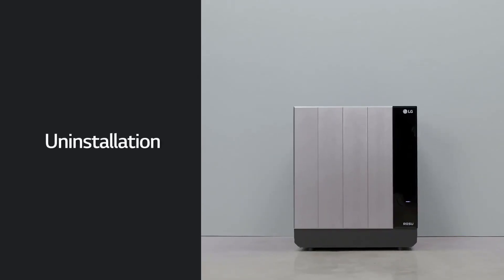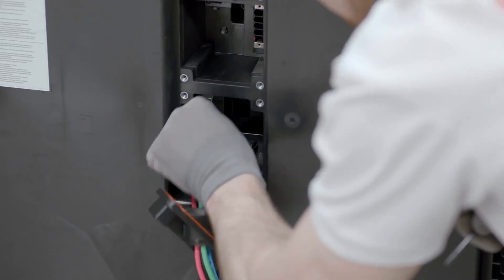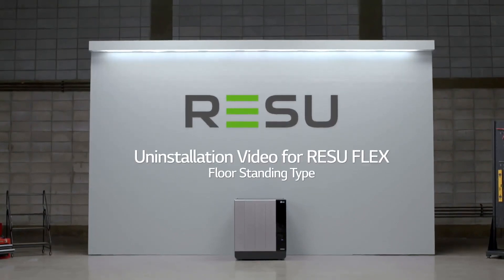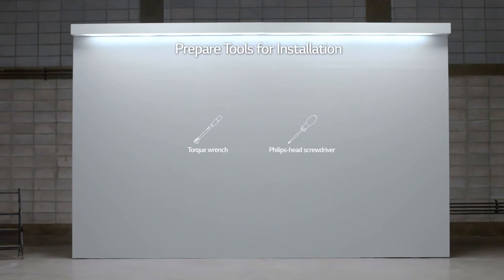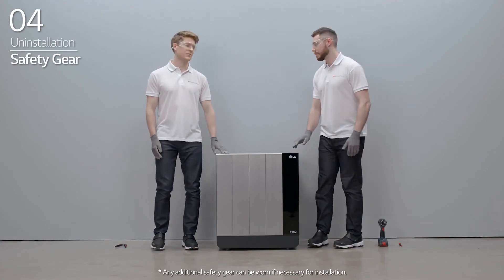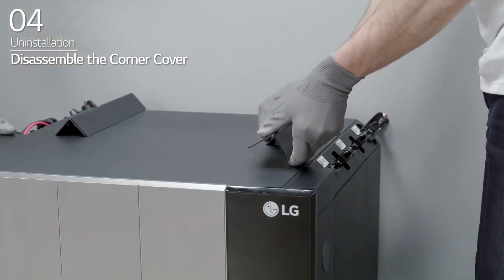Uninstallation. LG Energy Solution will show you how to uninstall the RESU FLEX. Before uninstallation, please make sure to read the installation manual thoroughly. Prepare the tools for uninstallation. Note that the tools and cables necessary are not provided by LG Energy Solution. Wear the safety gear listed in the installation manual at all times. First, disassemble the corner covers on each corner of the BMA and BPU.